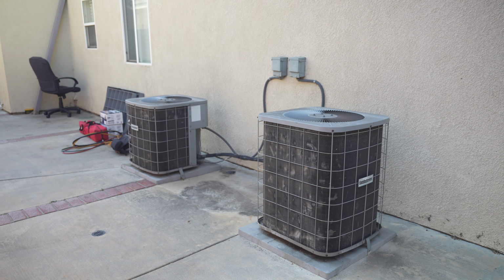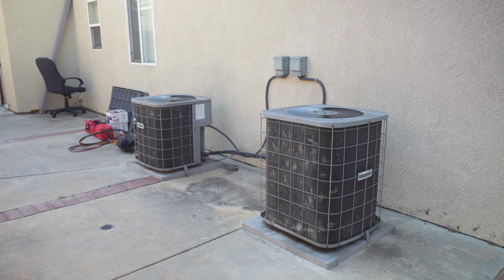A single stage system is going to be the most basic design. It has one operating speed, on or off. When it turns on, it runs at 100% of its capacity. And when the thermostat is satisfied, that system shuts off. So with single stage systems, it's either fully on or completely off. The pros is you're going to have a lower upfront cost. These are simple designs, easier to service, and proven reliability.